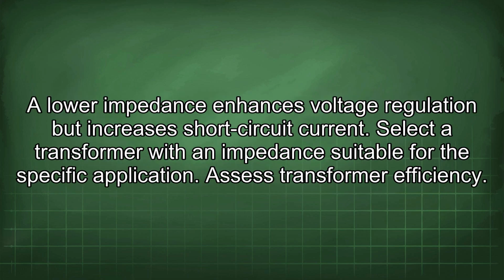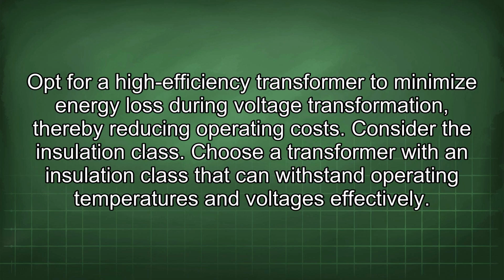Review impedance characteristics. A lower impedance enhances voltage regulation but increases short-circuit current. Select a transformer with an impedance suitable for the specific application. Assess transformer efficiency. Opt for a high-efficiency transformer to minimize energy loss during voltage transformation, thereby reducing operating costs. Consider the insulation class. Choose a transformer with an insulation class that can withstand operating temperatures and voltages effectively.